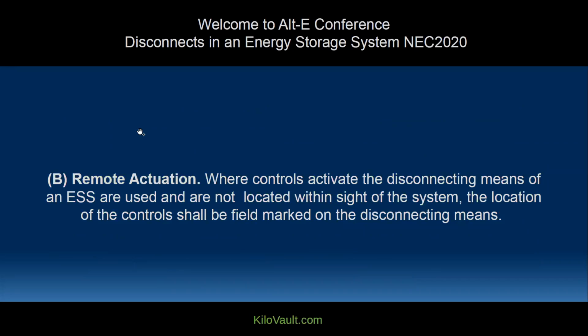All right, remote actuation: where controls that activate the disconnecting means of the ESS are used and are not located within sight of the system, the location of the control shall be field marked on the disconnect means. So if you're going to have that button or that switch outside of the two-family or single-family dwelling, there needs to be a field marking for that disconnect.